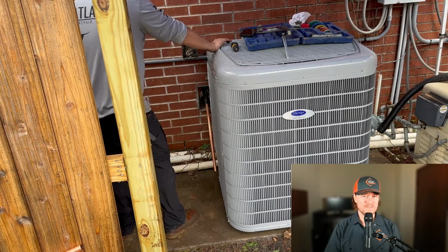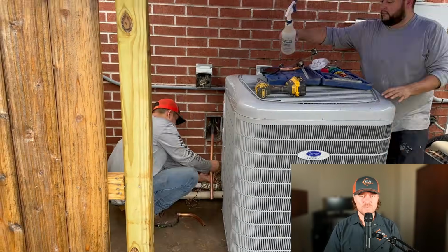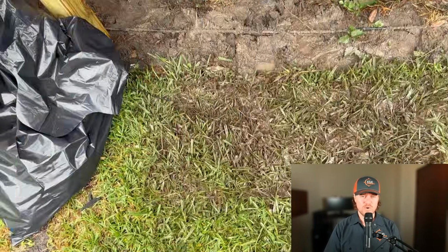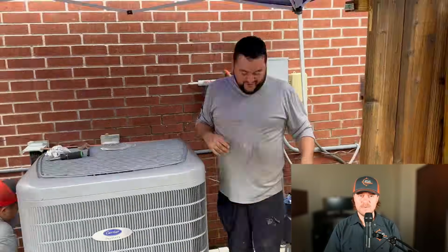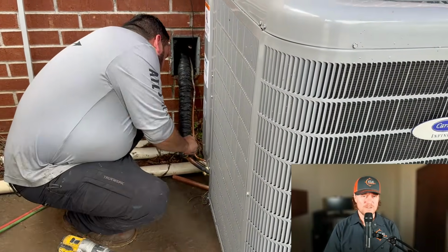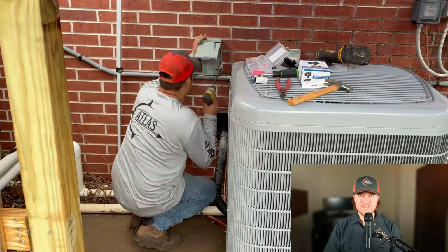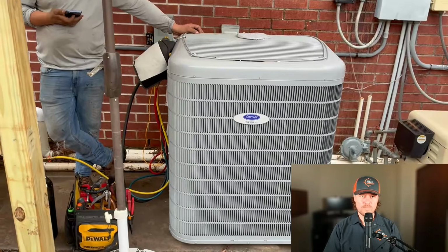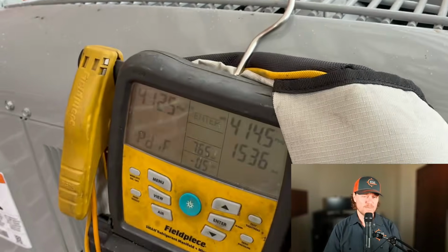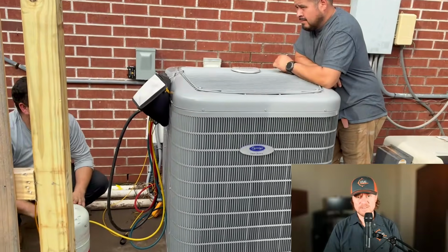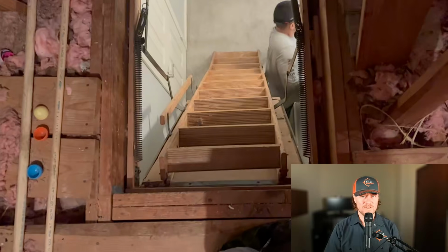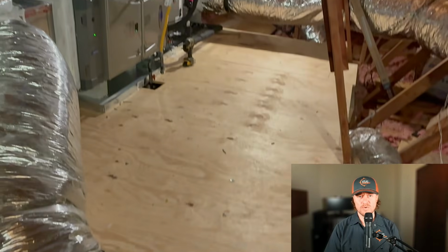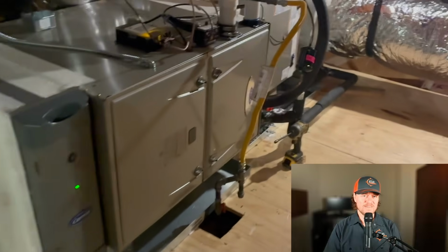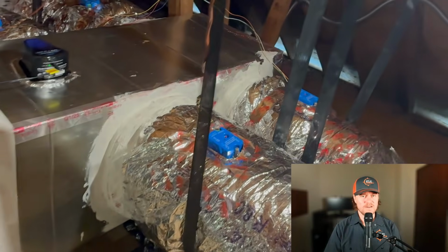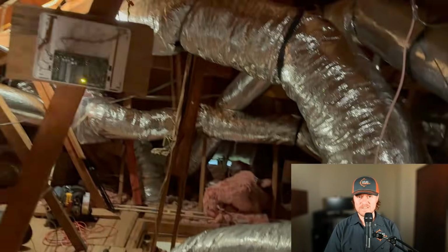If my house was balanced out correctly for non-zoning, it would look something like the upstairs would run 3 to 4 degrees warmer in the summertime, so it would be slightly undercooling, and the downstairs would be 3 to 4 degrees cooler in the wintertime, because the upstairs is now going to be slightly overheating. So basically, the upstairs is going to be 3 to 4 degrees warmer year-round. In an overly simplified explanation of the reason why, heat rises, so some of the downstairs heat is going to find its way upstairs, and some of the cooler air is going to fall downstairs. And the whole reason zoning was originally created was to fix this problem. That way, if you have the downstairs thermostat set at 72, along with the upstairs set at 72, now both the upstairs and downstairs are balanced out.